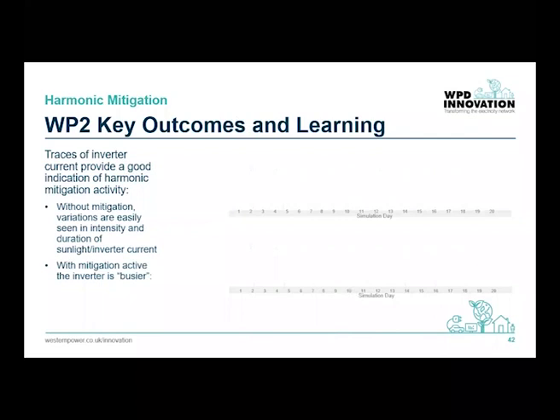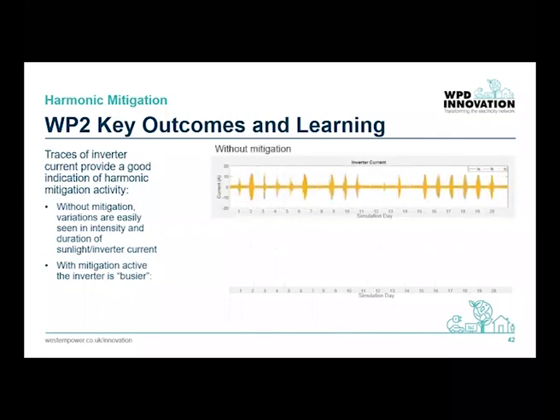The easiest way to see the impact of the mitigation controller is to look at traces of inverter current over the 3-week period. If we start by looking at the inverter's operation without harmonic mitigation, from the yellow trace of the inverter current, we see significant variations between days. Looking at day 2, we see it was sunny throughout most of the day, whereas day 1 saw less intense sun and for a shorter period. Perhaps the less said about days 11 and 12, the better. They were clearly very dull days.